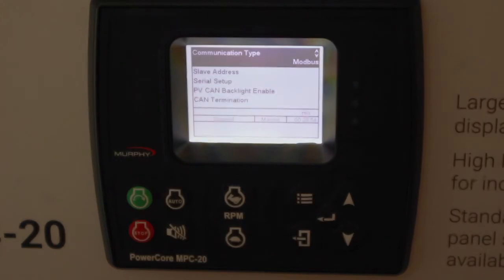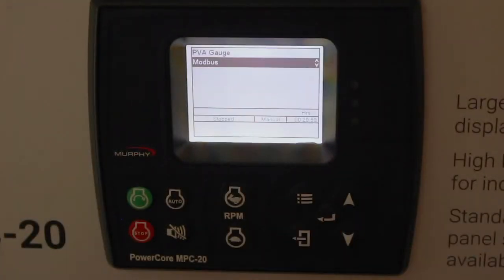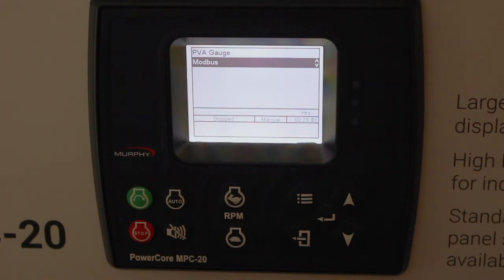The PowerCore family comes with an RS-485 port, and that port can be configured for two different types of communication. The default is Modbus, but you can also drive PVA gauges off the same port. You can't do both — so if you want to use Murphy Connect or somebody else's telematics to query our Modbus map for control and status, you would leave it on Modbus.